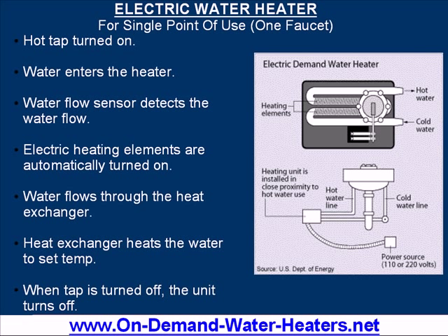Now for electric instantaneous or tankless water heaters, it's a very similar situation, where you have the water coming into the heater. There's also a flow sensor. The only thing is you don't have a burner, you have electric heating elements. And as long as there's flow, the heating elements heat up that water and then provide it to the faucet. As soon as the faucet is turned off, the unit recognizes that and turns off the electricity to the heating element. And in this picture, what we're showing you is a single point of use for just a sink, which is very common for an electric application, although you certainly can use it for a whole house application.